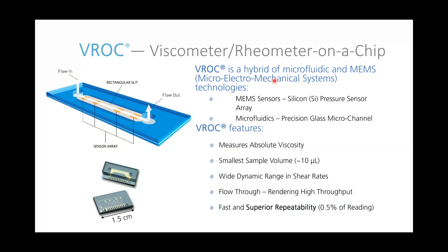The VROC of the VROC Initium is our core technology. It stands for Viscometer and Rheometer on a Chip. It's a hybrid of microfluidics and MEMS — a micro-electro-mechanical system — comprised of MEMS sensors, which are silicon pressure sensors, on a microfluidics glass chamber. This allows for measurements of absolute viscosity. The chip itself only requires at least 10 microliters of sample to get a full measurement. Depending on the chip style, you can have a wide range of different shear rates and flow rates. It's a through-flow system allowing for high throughput, with high repeatability of 0.5%.